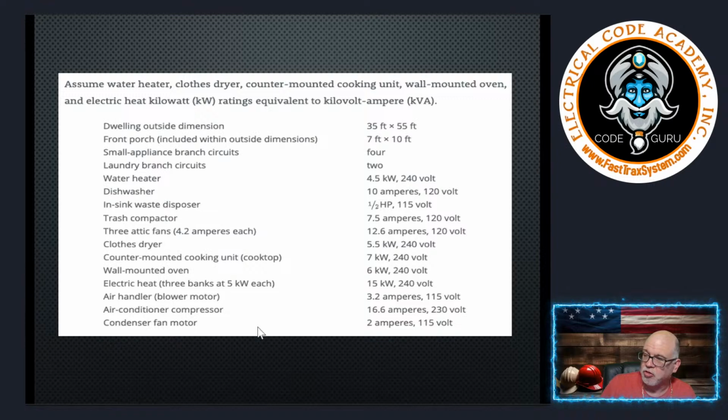All right? So it's only the 240 volt loads, except for the range and the dryer, which obviously you electricians are familiar with, right? We're going to run 4 conductors to those, and they have some elements in there that are going to need 120 volts, right? So definitely we're going to have some neutral loads associated with the dryers and the ranges. So we will take care of that as we move through it. But just so you know up front, they're going to be at 70%. And we get that allowance in 220.61(B). So anyway, we'll work through those type of things.